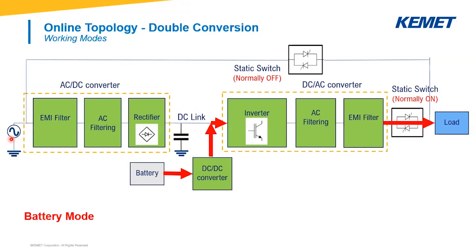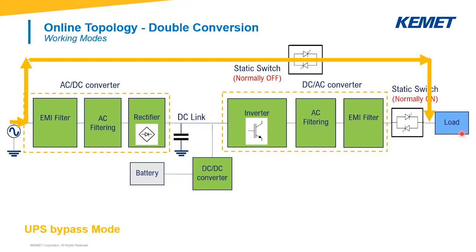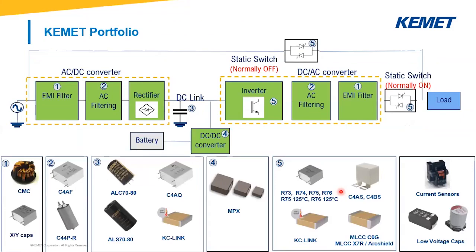During battery mode — invoked as soon as we have a failure on the mains or a loss of input power — power is taken from the battery and follows the path: DC-DC converter, DC-AC converter, then the load. Finally, the third mode is the UPS bypass mode. In this case, the entire UPS is bypassed and power is taken from mains. This mode could be used in case of UPS failure, but also during maintenance of the UPS itself.